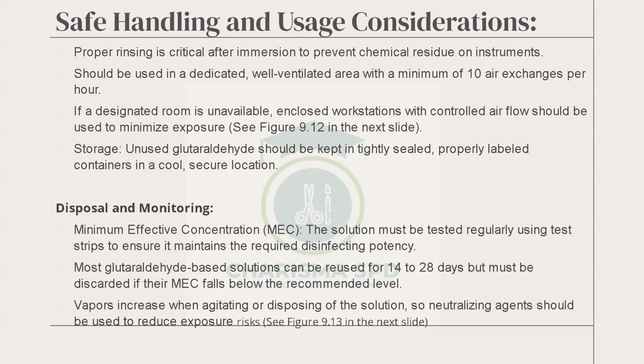manufacturer. But glutaraldehydes are always within this range. Anyway, most glutaraldehyde-based solutions can be used, but must be discarded if their MEC falls below the minimum. So the testing is always a test strip. It's a very small test strip. Now, you are not going to say that this must be there for 14 days, but the MEC has failed, but of course it's 14 days, so I'm going to use it. No. Even if you started using it today, and by tomorrow the minimum effective concentration fails, you must put it away.